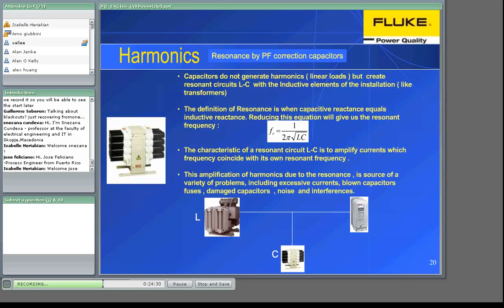In case a nonlinear load generates a harmonic signal whose frequency corresponds to the LC frequency, then this harmonic frequency will be amplified. This amplification of harmonics, owing to the resonance, is a source of a variety of problems, including excessive currents, blown capacitor fuses, or damage to capacitors, which can even explode.